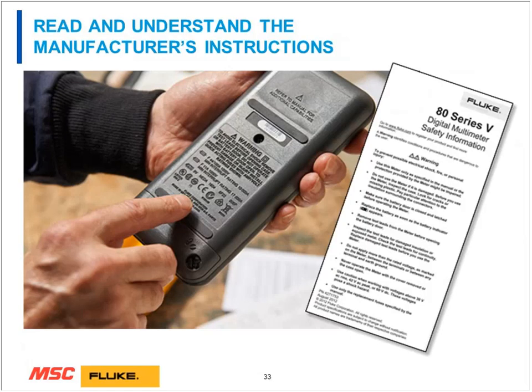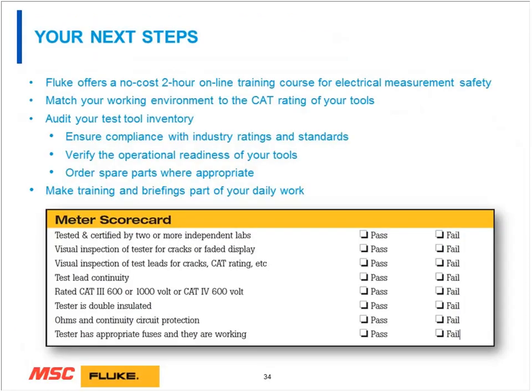Bottom line, read and understand all of the manufacturer's instructions on the instrument that you're going to use. That's essential. Next steps for you. We only have a couple more slides. One of them, we have some training that's available online. We have electrical measurement safety training. We have some DMM training, motor drive training, insulation tester training. Go to fluke.com, and under the training tab at the top, go to online training. We don't charge for it. Phenomenal training that'll bring you up to speed on using the instruments correctly and being safe when you're making those measurements.